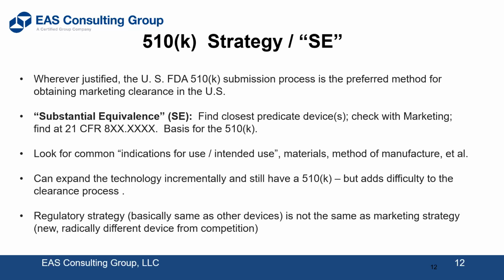And the purpose of the STEP program and the Breakthrough Devices program is to push that even a little bit further and to eliminate the difficulty in the clearance process. I know I pushed the envelope one time on a needle which had multiple fenestrations on the shank or the cannula, as opposed to a normal needle with just a hole at the end. And we had data to show that this was a safer device than the existing needle for anesthesiology. But what happened was the FDA looked at it, refused to accept the 510K, and told us we needed to do clinicals. We did a feasibility study, and it came out flawless.